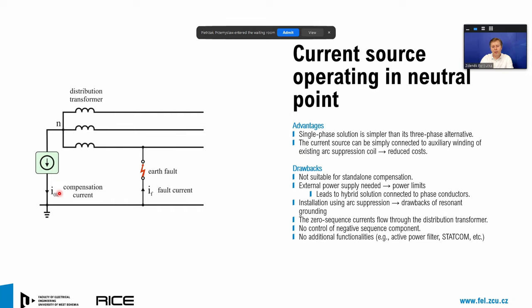On the other hand, there are plenty of drawbacks of this location of the active current source compensating the fault current. This solution is not suitable for standalone compensation because we need an external power supply, and it also brings us quite strict power limits. Moreover, the installation using the auxiliary winding of the arc suppression coil still has the problems of resonant grounding. So we did not overcome one of the problems of the passive compensation of the fault current. The zero sequence current still flows through the transformer, obviously, and there is no possibility to control the negative sequence component. And of course, we are unable to provide the grid with the additional functionalities which the alternative solution can offer.